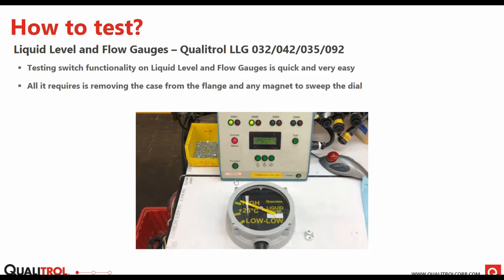And we have some videos here for testing to kind of simulate it, or to show you how easy it really is. So testing a liquid level gauge or a flow gauge, all you really need to do is remove the case from the flange. So most of the time there will be 4 set screws on the side of the case. So what you see here is the case portion of the liquid level gauge. They're magnetically coupled, so magnetically driven.